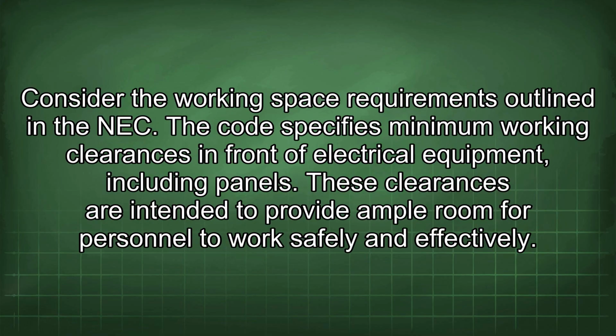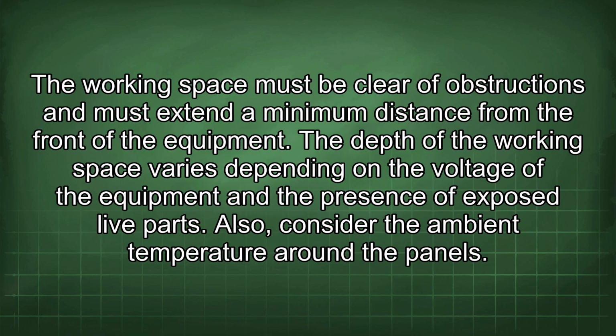Consider the working space requirements outlined in the NEC. The code specifies minimum working clearances in front of electrical equipment, including panels. These clearances are intended to provide ample room for personnel to work safely and effectively. The working space must be clear of obstructions and must extend a minimum distance from the front of the equipment. The depth of the working space varies depending on the voltage of the equipment and the presence of exposed live parts.